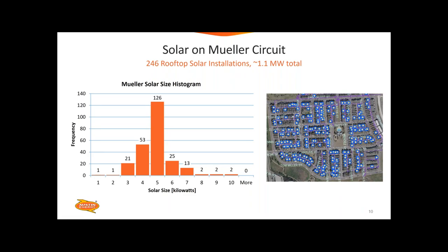To give you an idea of the level of solar penetration we have at the Mueller neighborhood, here's a graphic illustration of the different rooftops that have solar. We've got approximately 246 rooftop installations on this feeder, totaling about 1.1 megawatts of installed capacity of solar PV.